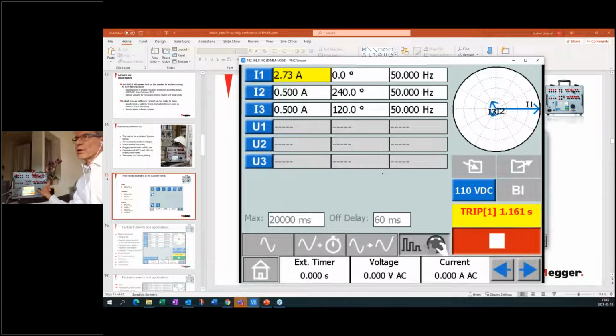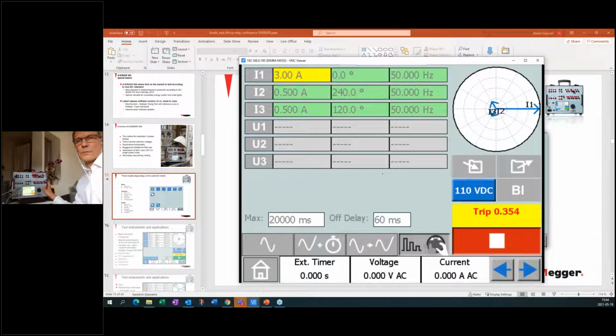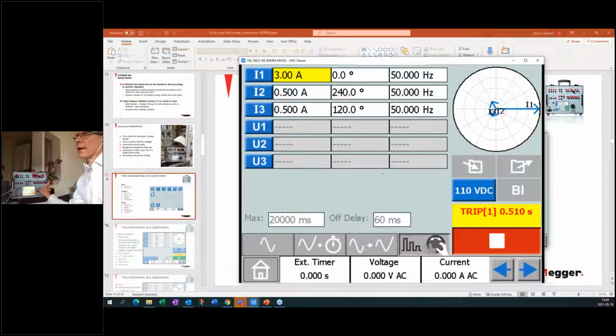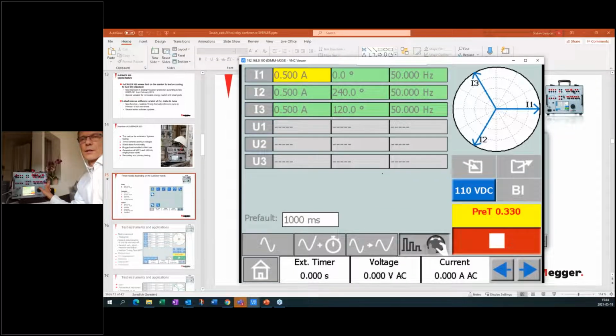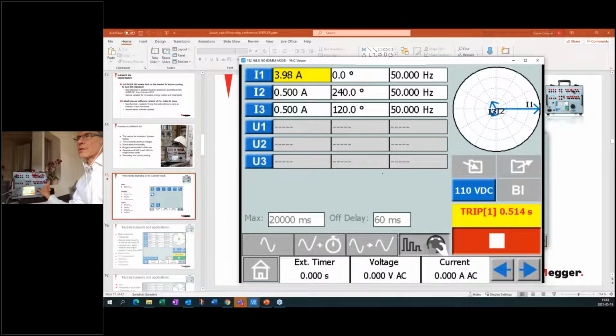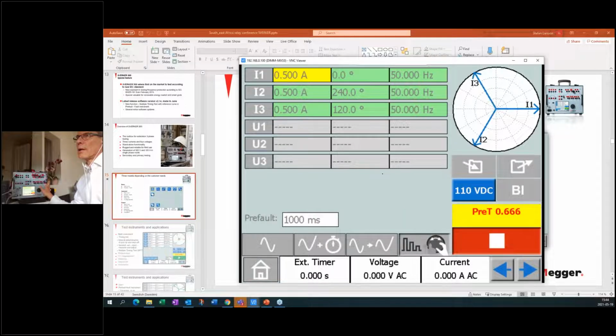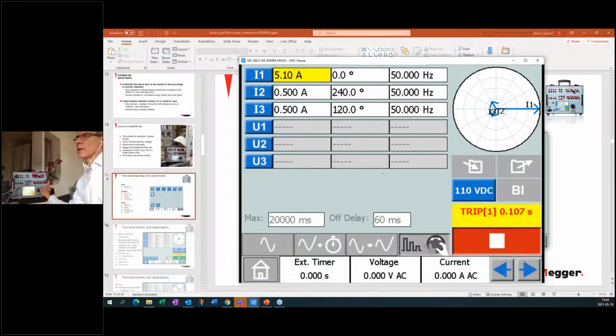So the first level is inverse, and the next level starts at 3 amps. It's definite time. It should be 500 milliseconds according to the relay setting. And I take 2 shots on that threshold. And actually we have 3 thresholds in this case. So I will go up to the highest threshold, and that's 5 amp. And at this 5 amp, we will have around 100 milliseconds. So that's the threshold there. I take 2 points there.